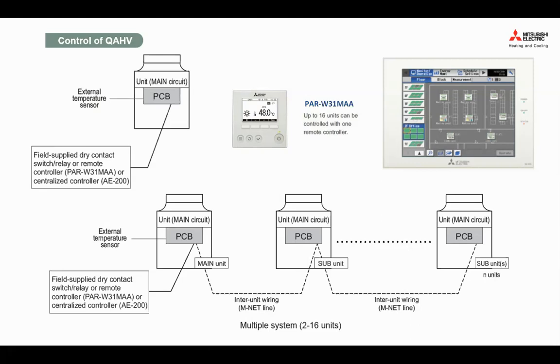And you can also connect up to 16 units. So from 2 to 16 units, you can daisy chain them, and they will be able to communicate internally from the main unit to the subunit, as well as communication between the subunits through the M-NET line. And then you can have dry contact to switch on and off, or set temperature, or send a signal for the unit to operate and react to what's required on the site.